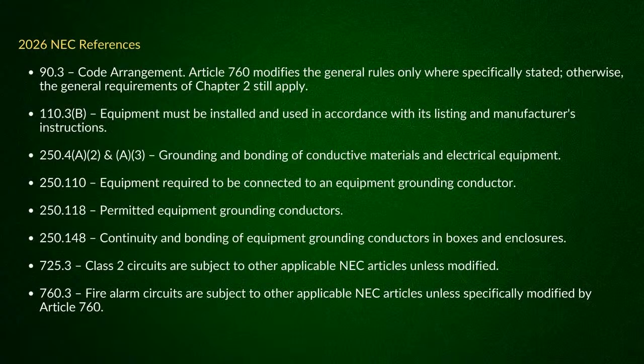Well, see, when you get over and look at 112 and what that gets into, they talk about fire alarm circuits shall be grounded, but it refers you to systems that have been grounded. So depending on what type of system you're coming from, it'll tell you to go see part 2, which is system ground, then part 8, which is DC ground.